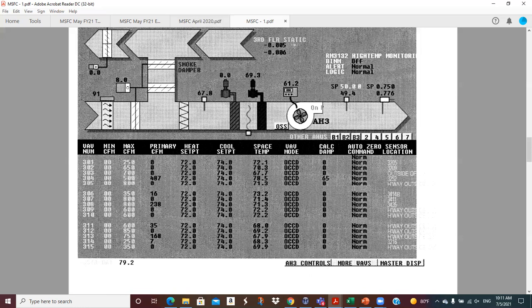But the way you look at it, this is the 3rd floor. This is return air that's coming back, and it looks like it's closed. That would be if we're going to exhaust this air from the building, the return air. So if that's closed, then the return air has to come back into this chamber. This is outside air, ventilation air. If we can get in this chamber, this is what we would want to measure: note the damper position and try to measure this. And if we're in there, we can measure this too. These are just louvers: the more open this is, the more closed this is, and the more closed this is, the more open this is. We can potentially go on free cooling with outside air with this, called an economizer cycle. So this looks like, I guess that's 91 degrees. I think this is a position.